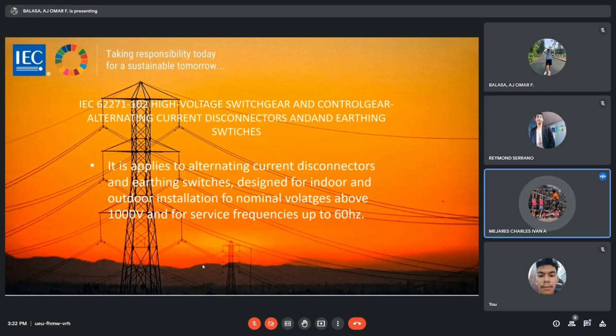IEC 62271-102, high voltage switchgear and control gear, alternating current disconnectors and earthing switches. It is applied to alternating current disconnectors and earthing switches designed for indoor and outdoor installations for nominal voltages above 1000 volts and for service frequencies up to 60 Hz. It applies to the operating device of these disconnectors and earthing switches and their auxiliary equipment. It is also applicable to switching devices having disconnecting and earthing functionalities apart from other functions, such as high-speed earthing switch, circuit breaker, and switch disconnector.